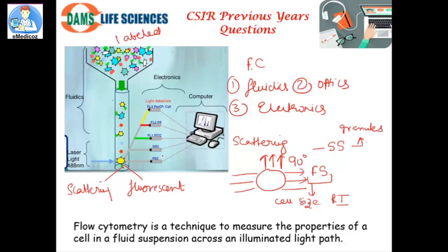The forward scattering collector captures light at the same angle as the laser, while the side scattering collector captures light deflected by 90 degrees. You also have specific detectors for fluorescent dyes — one for FITC, one for phycoerythrin (PE), and so on. So you can measure both scattering and fluorescence.